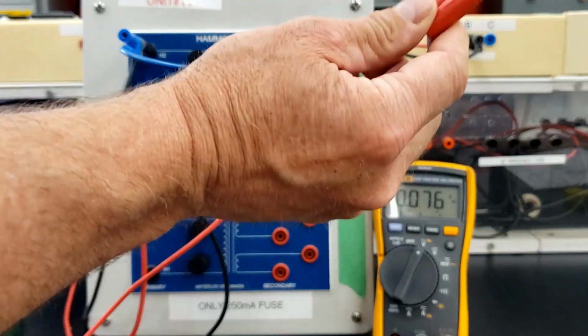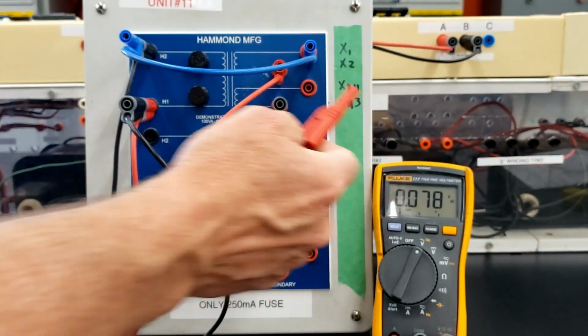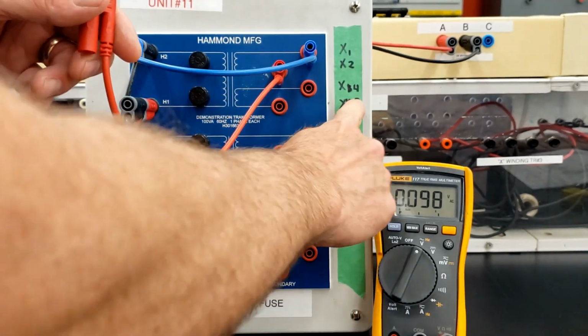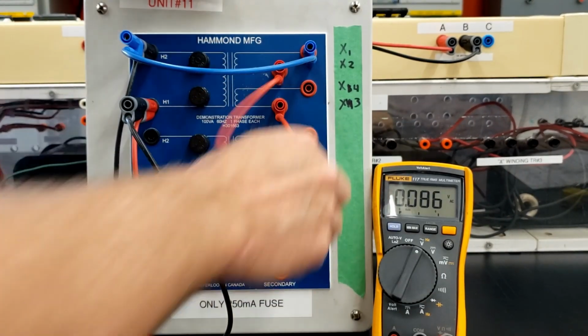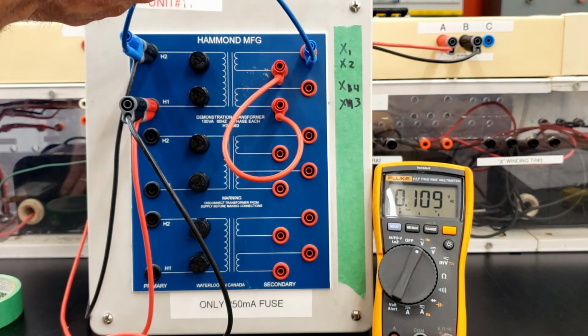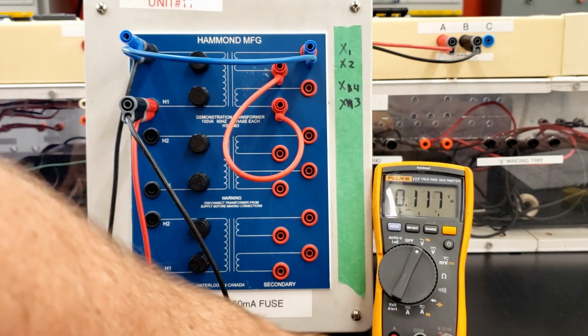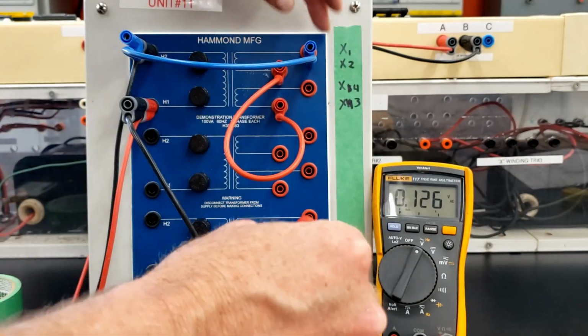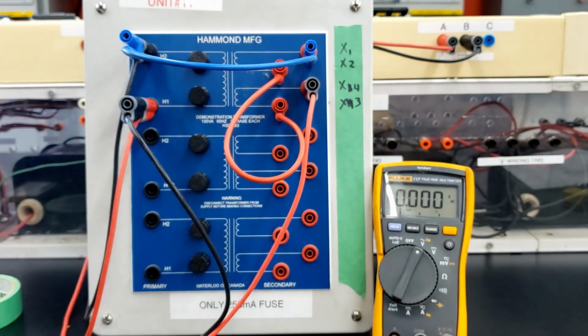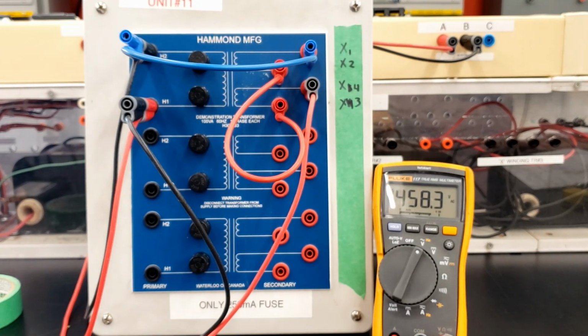Power's off. I'm taking that jumper that I had from what I thought was X2 to X3 and moving that over to this terminal right here now. Okay, I still have the connection between the primary and the secondary. I've got this connected up in what I hope is an additive voltage, in that the primary and the secondary voltages are going to sum together. And I'm going to take the voltage now between H1 and X4. Oh yes. Okay, so now we've got the additive voltage, 458 volts.